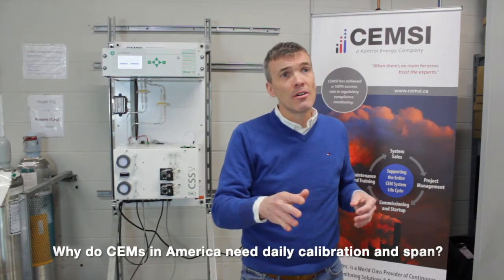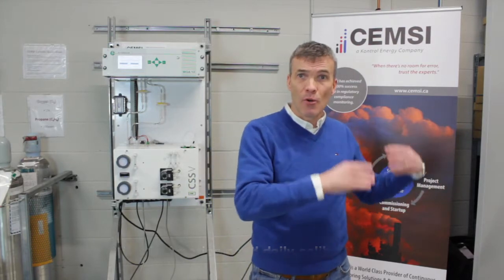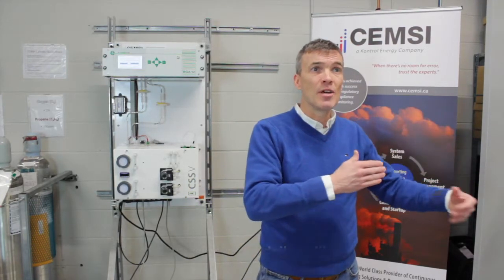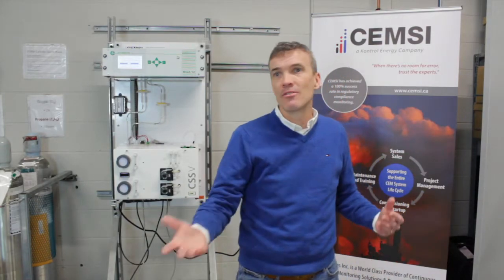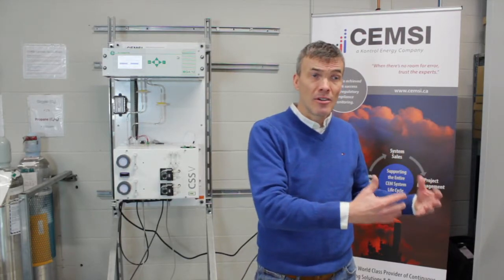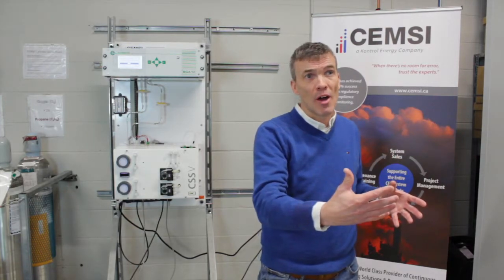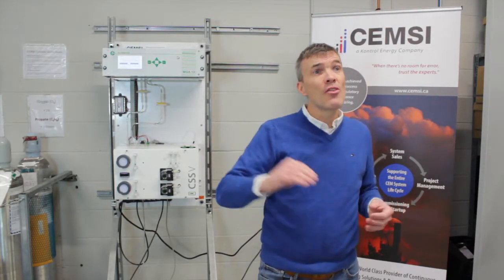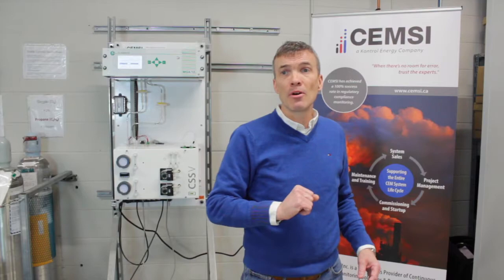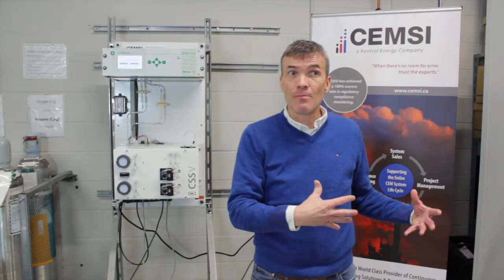And then every quarter, you are going to do another set of tests called cylinder gas audits, where you're basically going to take 3 additional bottles for each component you're measuring, and you're going to inject them 3 times each. And I know this starts getting confusing, but it gets confusing for our customers as well. So you have to do all this testing to prove that the linearity is correct. And then on top of that, on an annual basis, depending on where you are geographically, sometimes every 6 months, you have to have a third-party group of people come wheeling in with a truck full of analyzers and full of wet chemical analysis to actually analyze your stack gas and compare it with what you're getting on your analyzer.